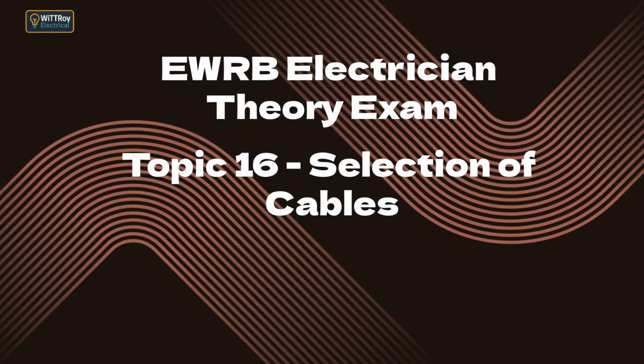Bringing it all together. To bring everything together, cable selection is a systematic design process. We identify the load, choose the correct installation method, apply all derating factors, and confirm voltage drop, loop impedance, and short circuit performance. For mains and submains, we also calculate maximum demand. Every step ensures the cable remains safe under normal operation and during fault conditions. When you follow this process consistently, choosing the correct cable becomes straightforward and fully compliant with the standards.